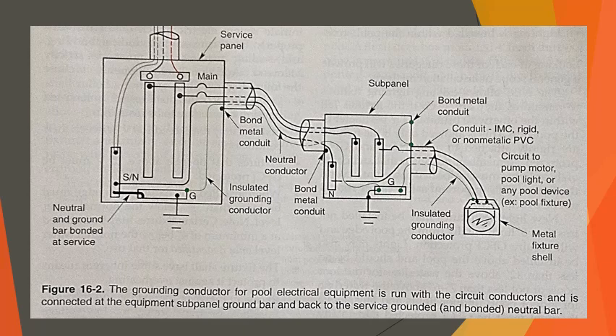Grounding. In addition to bonding, all electrical equipment related to the pool and within 5 feet of the interior walls must be properly grounded. This creates a low resistance pathway for fault currents to get back to the neutral so that fuses or circuit breakers will operate correctly. The grounding conductor must be properly sized for the particular circuit as listed in NEC table 250.122. It cannot be smaller than 12 AWG copper.